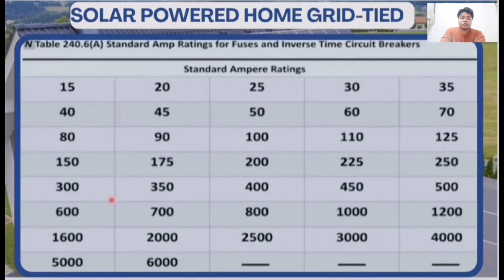Ngayon ay ipapaliwanag natin ang breaker sizing para sa solar photovoltaic system at ang kahalagahan nito sa safety at reliability ng buong installation. Ang breaker sizing ay isang mahalagang bahagi ng electrical design ng solar PV system. Dahil dito, ang nagsisilbing protection ng circuit laban sa overcurrent, short circuit, at iba pang electrical faults. Sa tamang breaker sizing, masisiguro natin ang kaligtasan ng mga equipment at maiiwasan ang posibleng hazard tulad ng overheating. Ayon sa Philippine Electrical Code, ang current sa solar PV system ay itinuturing na continuous load.